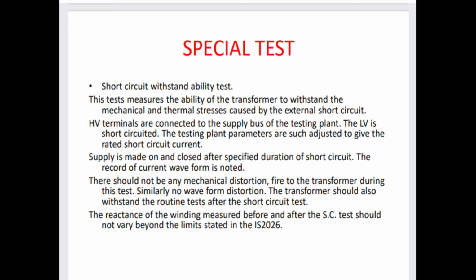And so here we see the special test. Here we see the short circuit withstand ability test. This test measures the ability of the transformer to withstand the mechanical and thermal stresses caused by the external short circuit. HV terminals are connected to the supply bus of the testing plant. The LV is short circuited. The testing plant parameters are adjusted to give the rated short circuit current. Supply is switched on and closed after the specified duration of short circuit.